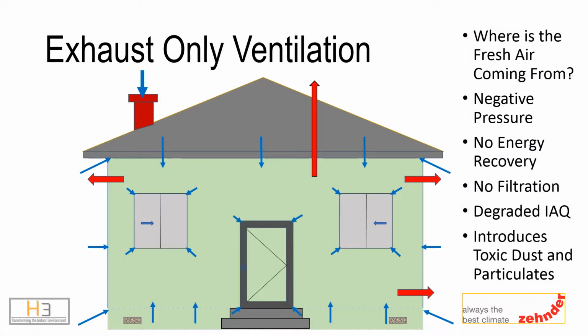Many construction professionals are still clinging to this concept by using continuous bath fans. This may be a cheap and easy fresh air strategy, but what are we doing? Where is this air coming from? Attics that contain dust, insects, and rodent droppings, crawl spaces that are dark, damp, and dusty. Negative pressure results in uncontrolled air and moisture being pulled into the home through walls and insulation. If the goal is to enhance indoor air quality, this is a serious failure. By the way, there is no energy recovery involved.